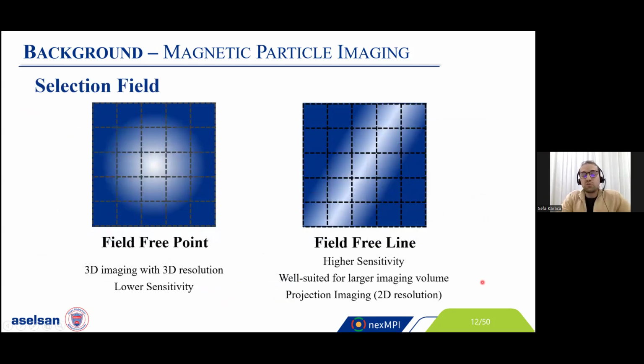So this selection field could be in the form of both field-free point or field-free line topology. And in our scanner, we utilize the field-free line topology because of the higher sensitivity and because it is well suited for larger imaging volume.